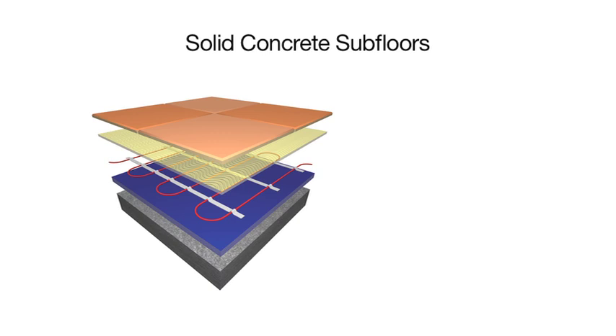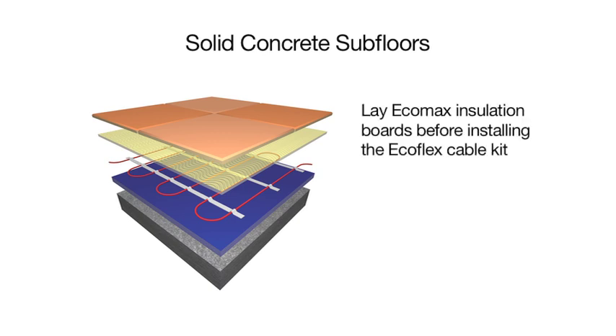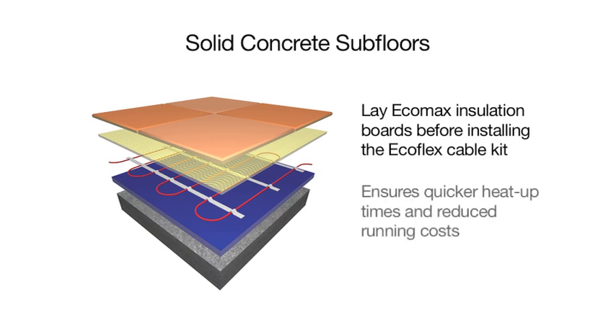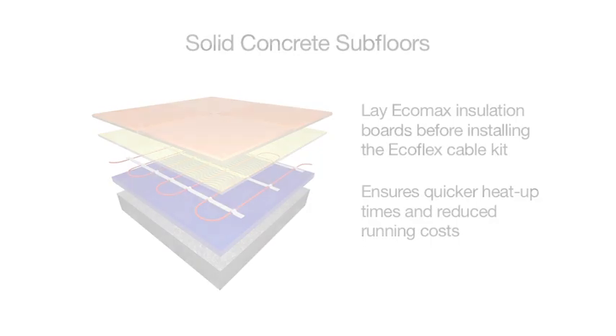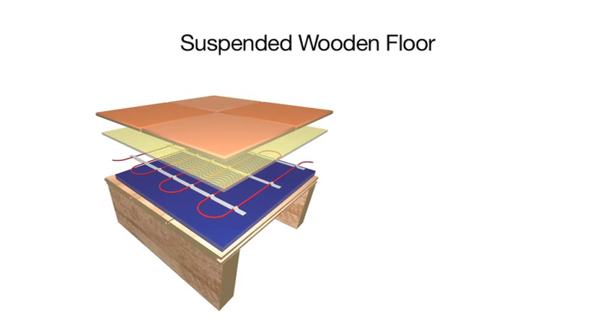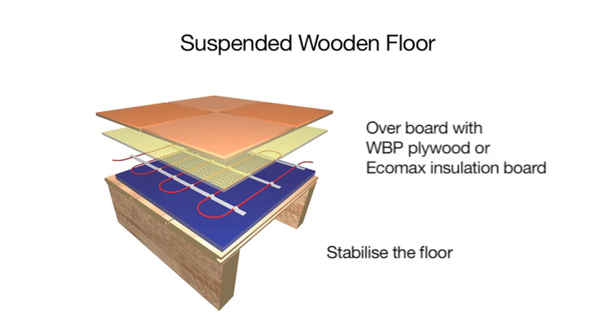Subfloors that have a rough finish should be prepared using a suitable levelling compound. On solid concrete subfloors, it is strongly recommended that EcoMax insulation boards are laid before installing the ECOFLEX cable kit. This will ensure quicker heat-up times and reduce running costs. On suspended wooden floors, it is essential that you take the standard precautions to stabilise the floor to prevent floor movement. You should always overboard a timber floor with a suitable surface for tiling.